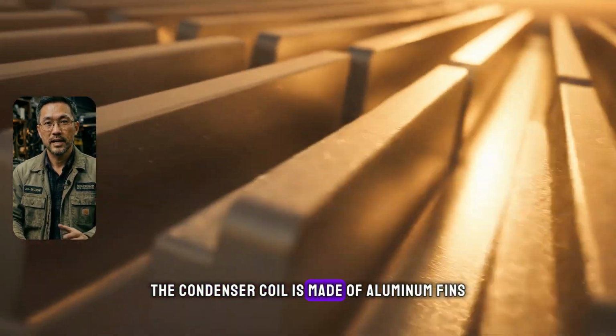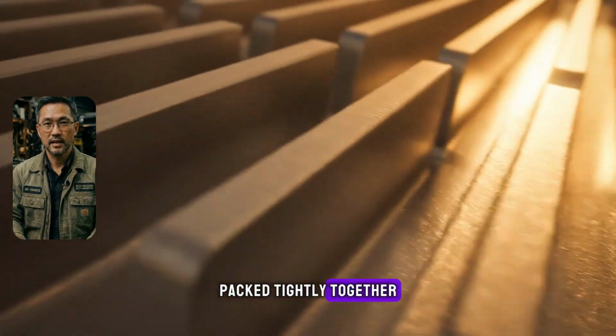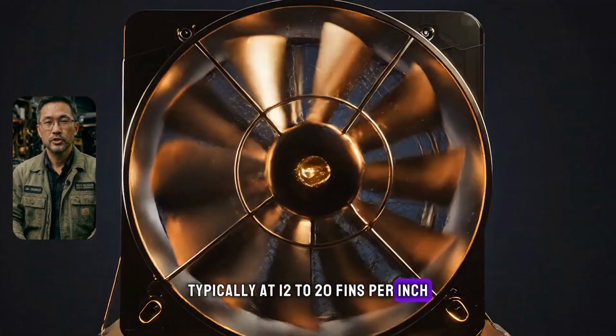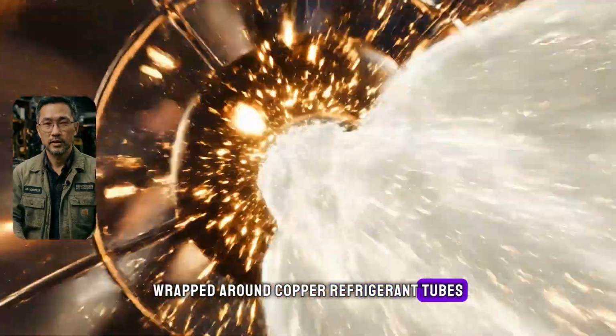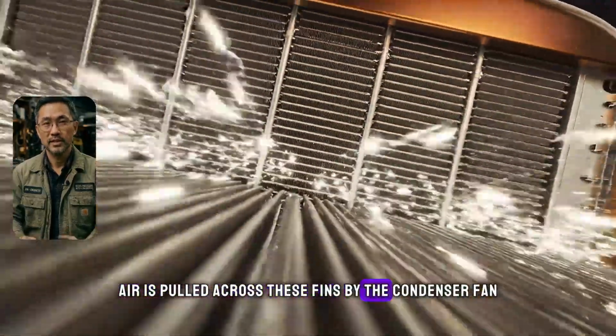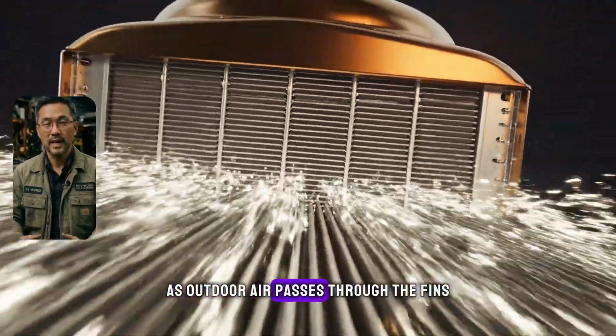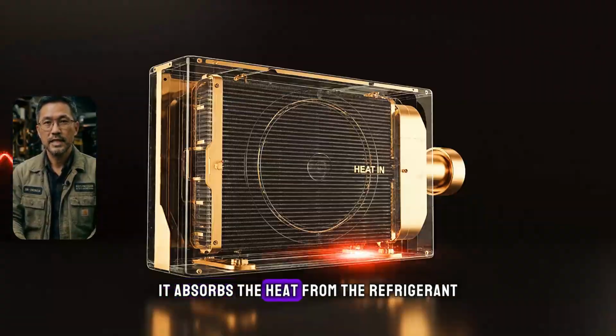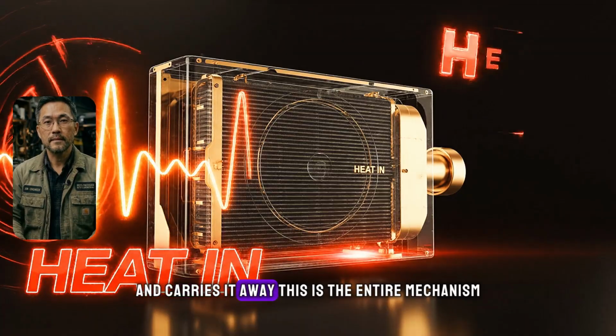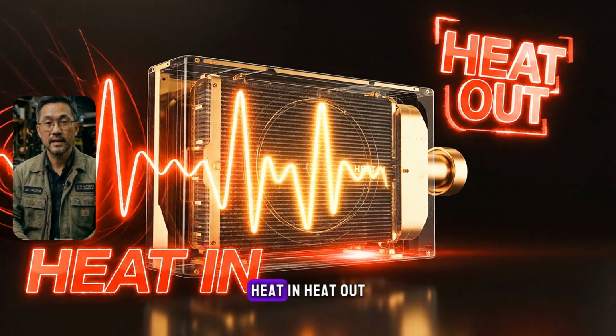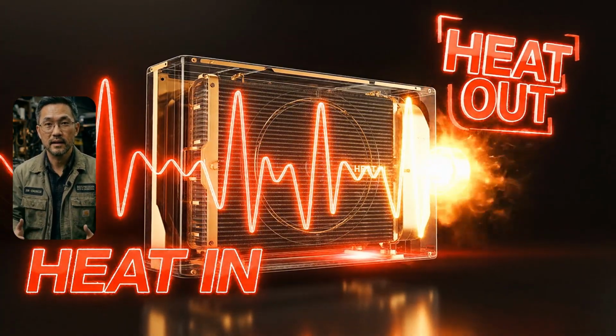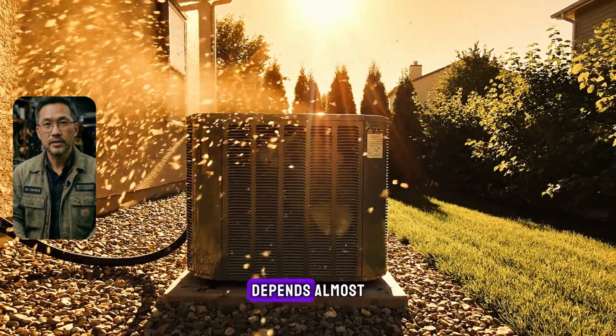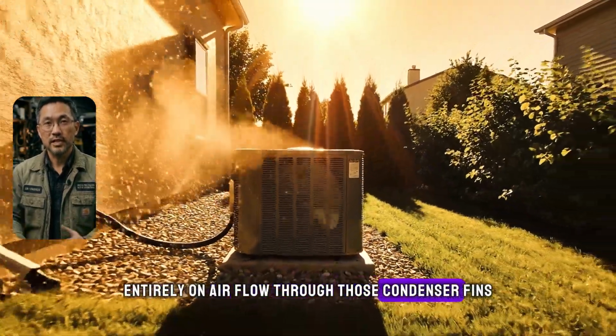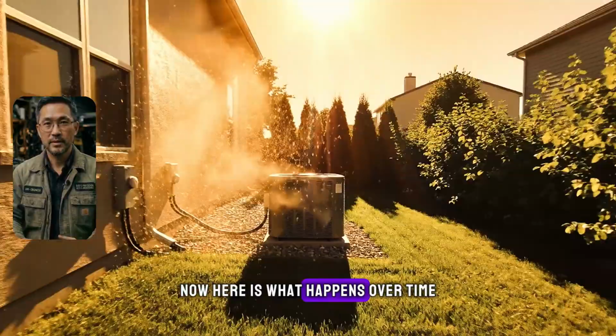The condenser coil is made of aluminum fins packed tightly together, typically at 12 to 20 fins per inch, wrapped around copper refrigerant tubes. Air is pulled across these fins by the condenser fan. As outdoor air passes through the fins, it absorbs the heat from the refrigerant and carries it away. This is the entire mechanism: heat in, heat out. The efficiency of this process depends almost entirely on airflow through those condenser fins. Now here's what happens over time.